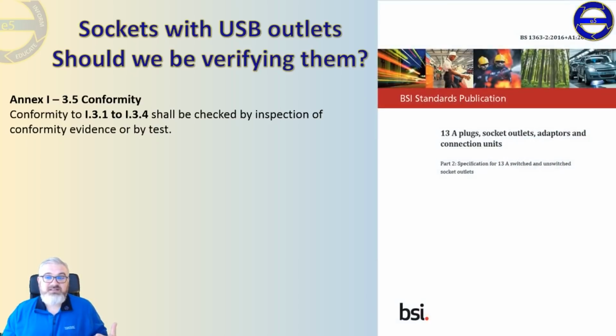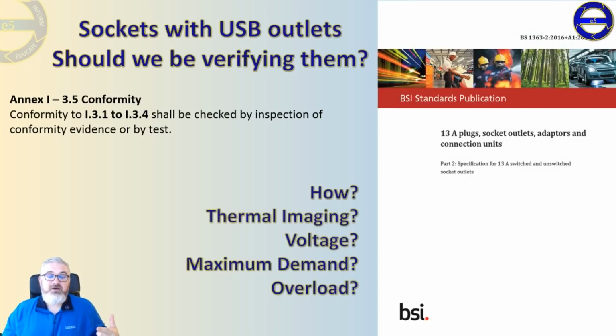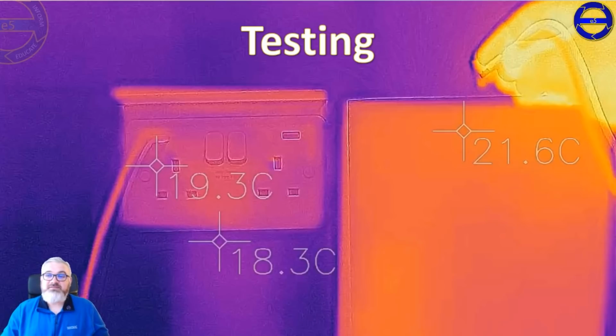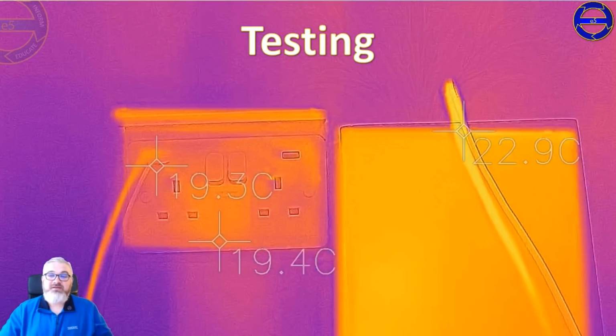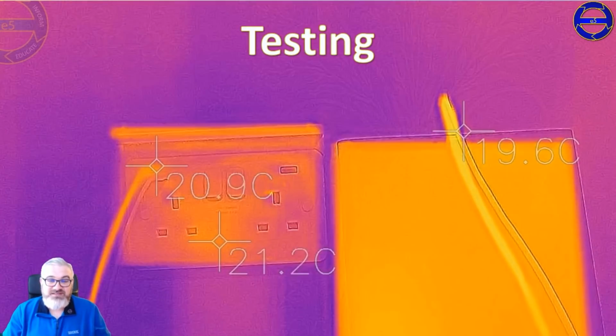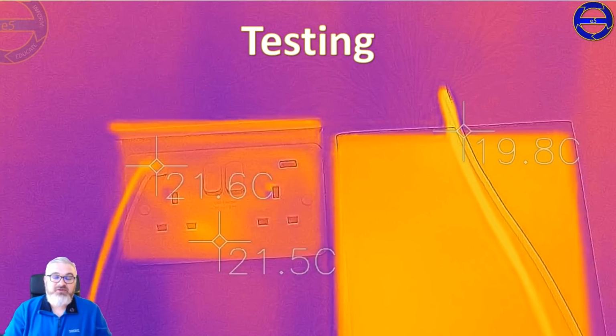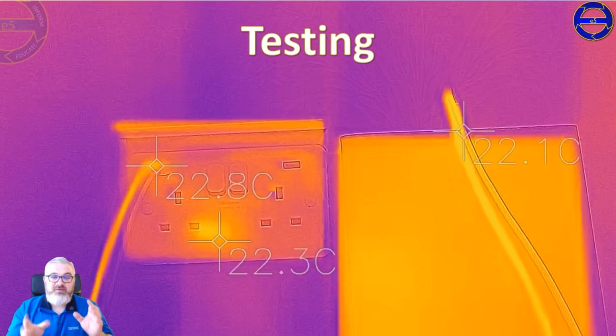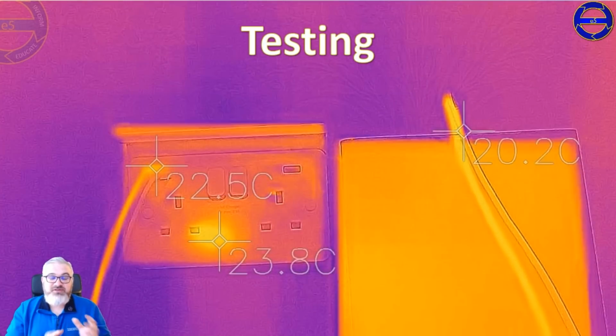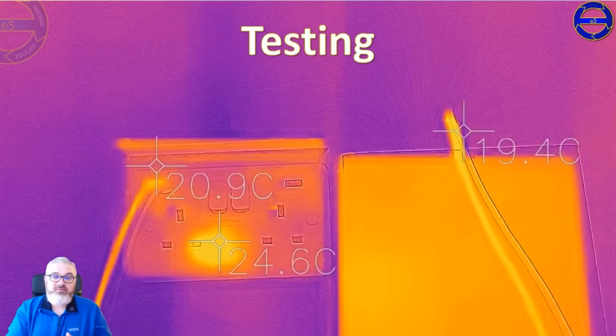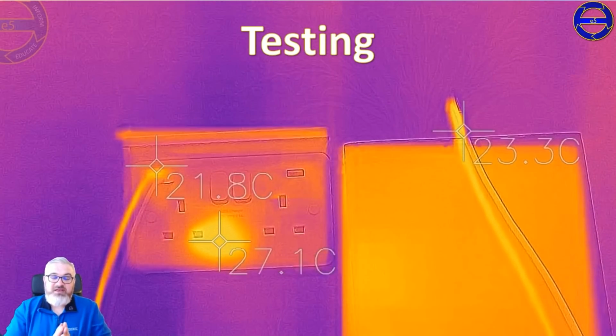So if we were to test it, then this standard particularly, what sort of test would we employ? So for me, I could do thermal imaging, I could look at voltage output, I could look at maximum demand, and I could do overload tests. But how would I actually do that? So let's have a look at a video. So this is me plugging in my iPad next to a Schneider Lisse socket, and as you can see, I've got the two spots there just to give me a bit of a benchmark on temperature differential. The 23 degrees at the bottom that's glowing orange, this is obviously sped up, is where the rectifier in the back of the socket is getting hot.